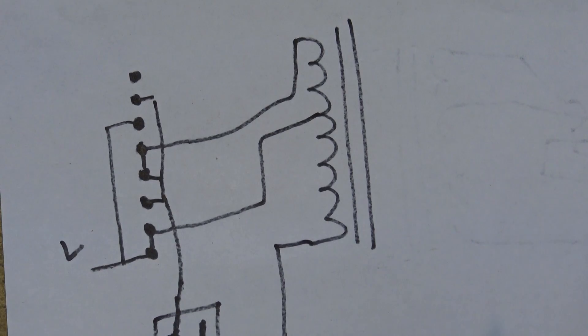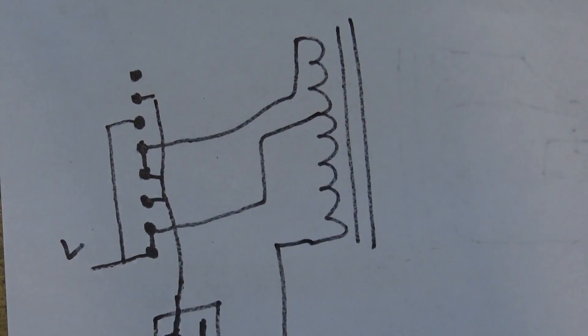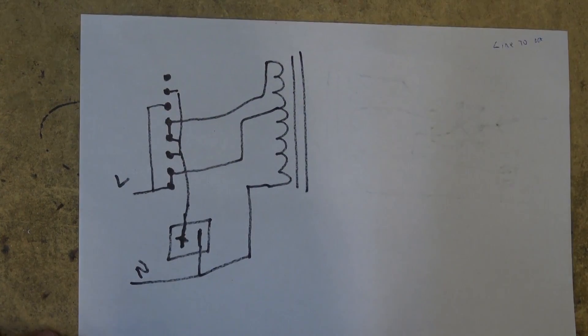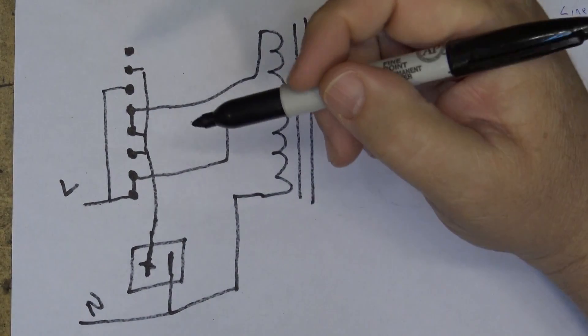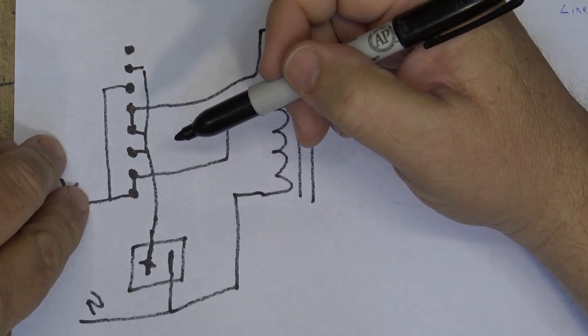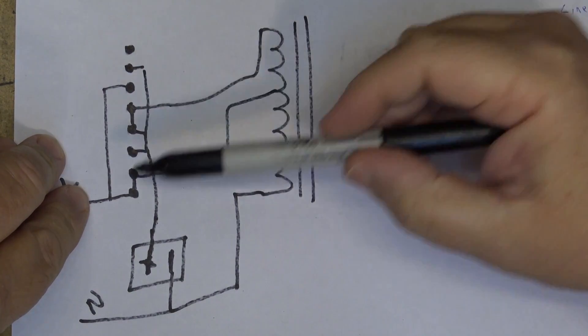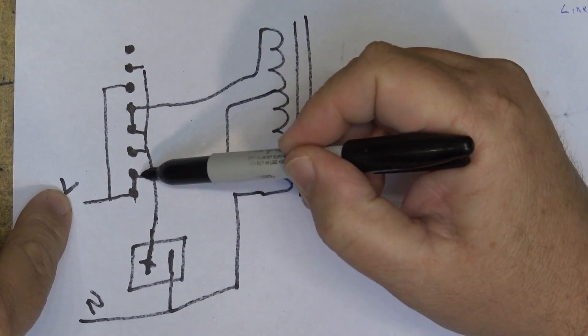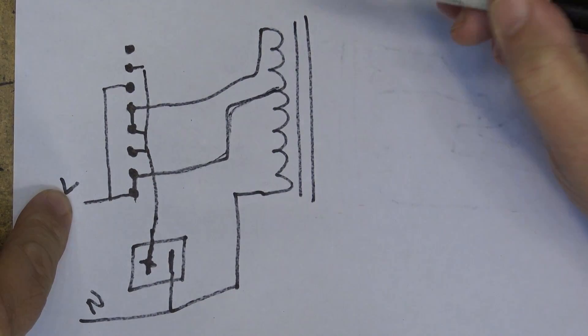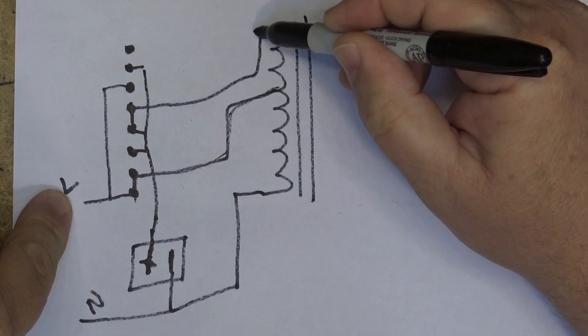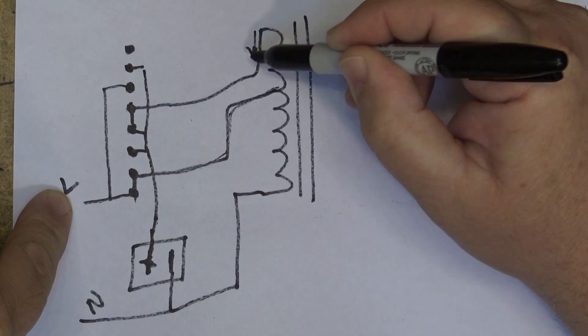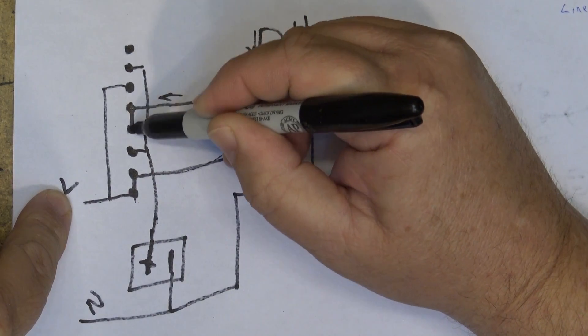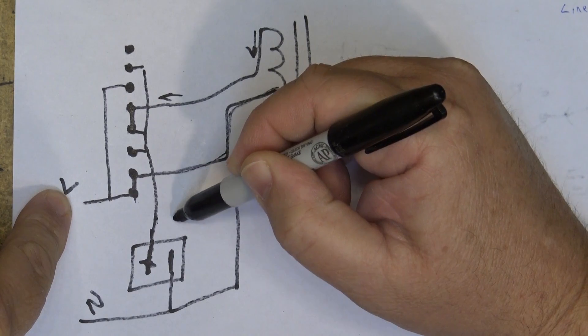Depending on what position the switch is in, if you're in the boost position you will be sending power from the line in. It's going to go up this direction here into the center tap of the transformer. It is going to come back out this direction into the switch which is now closed on this side, which is going to give you your boost.